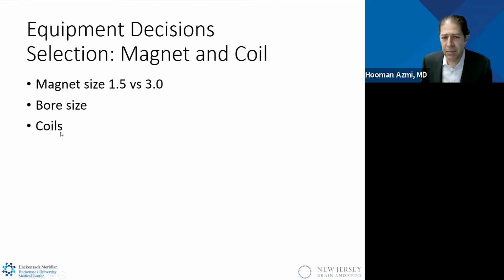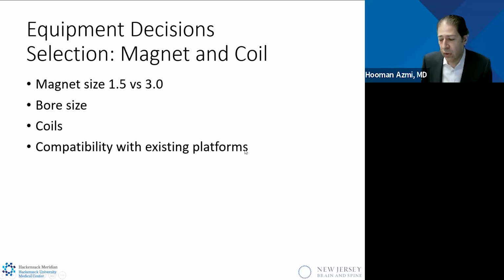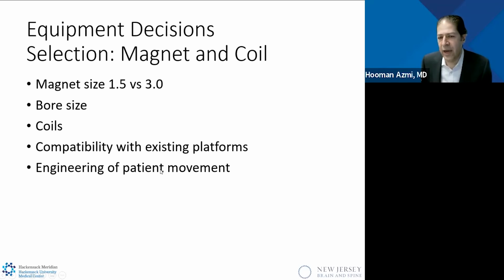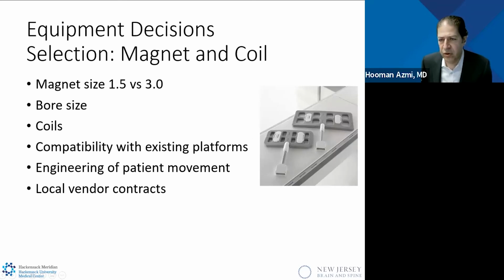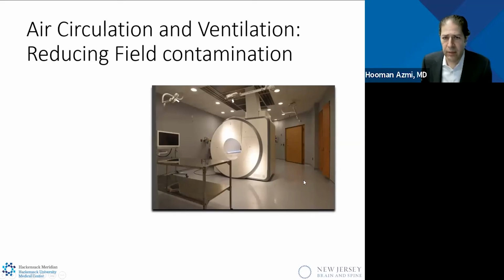Certainly, the magnet needs to be compatible with the coils that are available, and compatibility with existing platforms. For example, when MRI-guided focused ultrasound was initially developed, it was only with the GE platform, and Siemens was not able to use it. We use a Siemens machine. Other things, engineering of patient movement is very important. How patients move in and out for stereotactic procedures. Accuracy is very important. Siemens happens to have a very accurate chain movement, which is not there for the other vendors yet, although I hear that they're working on it. So that has something very important to do as well. And certainly local vendor contracts with the hospitals and the networks go into that. And this is a picture of our flexible coils that we use for our stereotactic procedures.